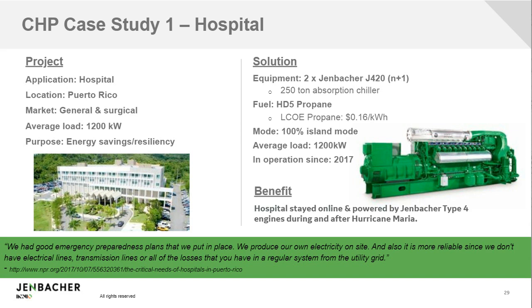And actually in this case, it's really a 2N configuration, since only one engine has to run at a time to satisfy the load. So the other is there as a backup. And when the first or primary unit is down for planned maintenance or for any other reason, the other one can come online and carry the load. So the hospital is never without one of those engines available.